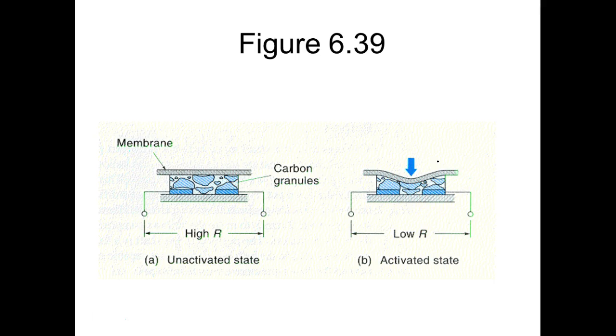What they would do is use a solenoid across a bunch of these carbon discs. As the voltage tried to go up, the solenoid would spread them out and cause the generator output to go down. And if it tried to go down, it would compress it.